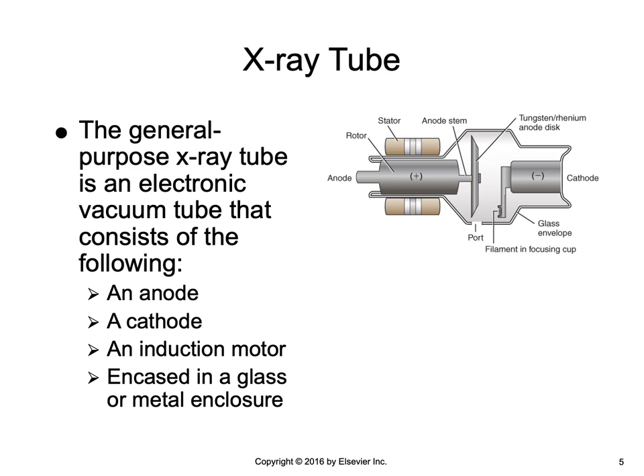The general purpose x-ray tube is an electronic vacuum tube and it consists of an anode, a cathode, and an induction motor, encased in a glass or metal enclosure called the glass envelope. The anode is the positive end of the tube and the cathode is the negative end. The anode incorporates an anode target and an induction motor, half of which is inside and half outside of the glass envelope. The cathode consists of the focusing cup and filament with supporting wires.